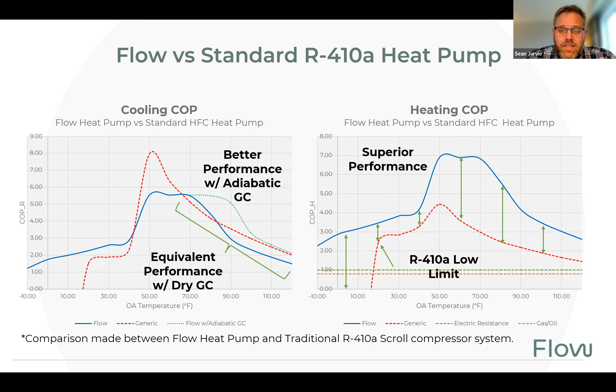And now on the heating side, because of that transcritical nature I showed you earlier, that system is anywhere from 20 to 40% more efficient on heating. Plus it has a lot bigger application envelope, where many systems either turn off at 20 degrees or start injecting liquid at 20 degrees into their suction gas to artificially raise that suction temperature in order to make it work longer. That seriously takes away from your capacity. And when you take away from your capacity and still use the same power, your COP drops like a rock.